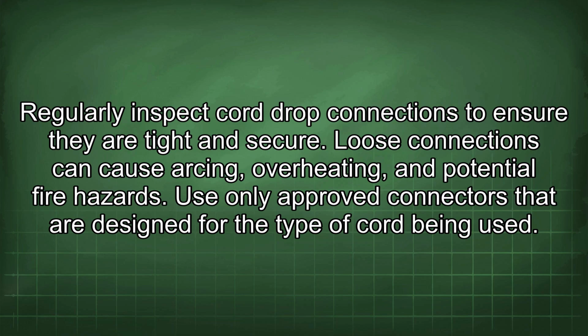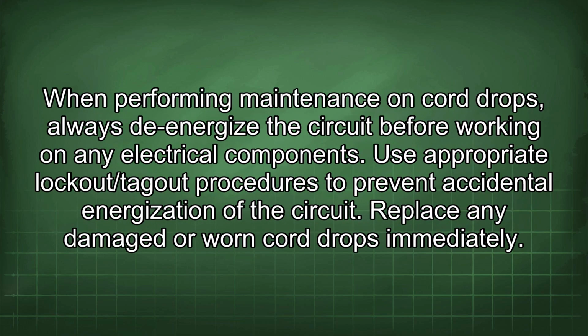Loose connections can cause arcing, overheating, and potential fire hazards. Use only approved connectors that are designed for the type of cord being used. When performing maintenance on cord drops, always de-energize the circuit before working on any electrical components. Use appropriate lockout/tagout procedures to prevent accidental energization of the circuit.